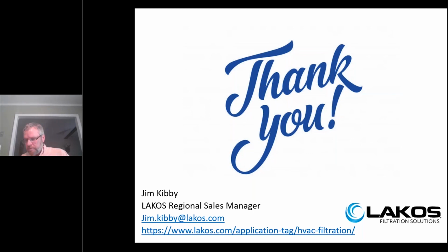It says, can you address the business case for using a TCX 25 micron particle removal versus a TCI as it relates to the fouling? You touched on corresponding energy use. In other words, how does separating smaller particles correlate to the reduction in fouling and subsequently save energy? It really depends upon the type of particle that you're dealing with. The particles that cause the most fouling are calcium carbonate, and the second that you turn the cooling tower on, you start evaporating water. The minerals don't, and the number one is calcium carbonate.